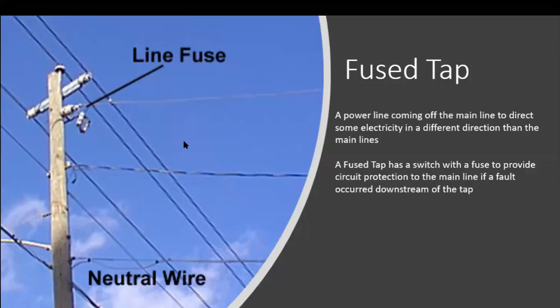All right, off our feeder line, we can have tap lines. So we can tap off the feeder if we need just to go a short distance and feed a small load off to the side here. So a fuse tap is a power line coming off the main line to direct some electricity in a different direction than the main lines. A fuse tap has a switch with a fuse to provide circuit protection to the main line if a fault occurred downstream of the tap.